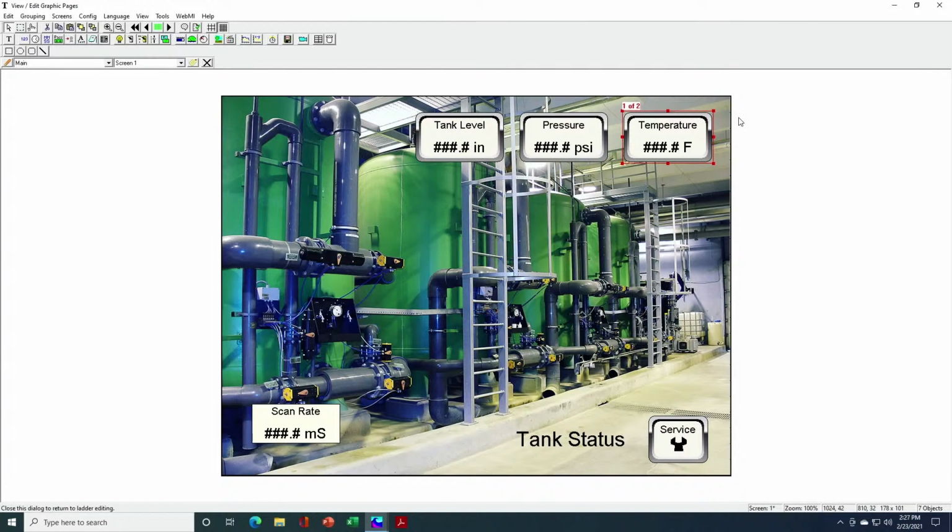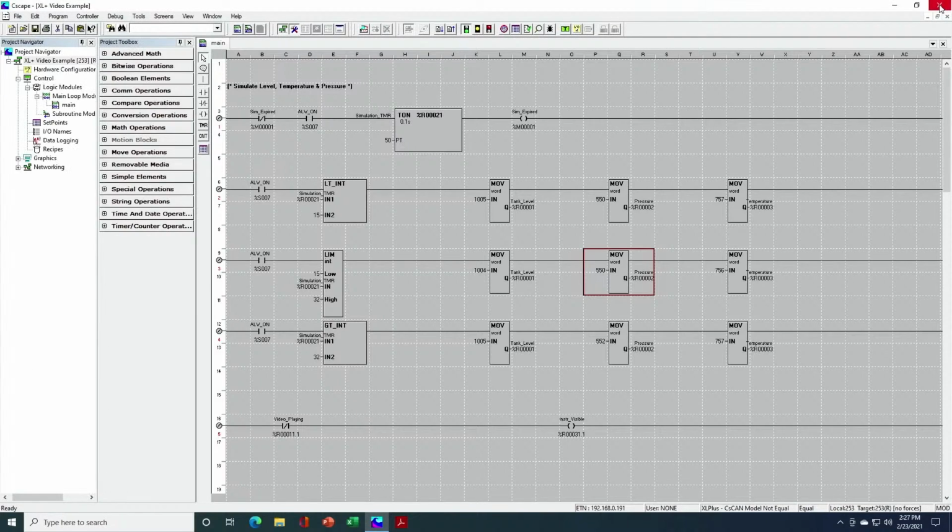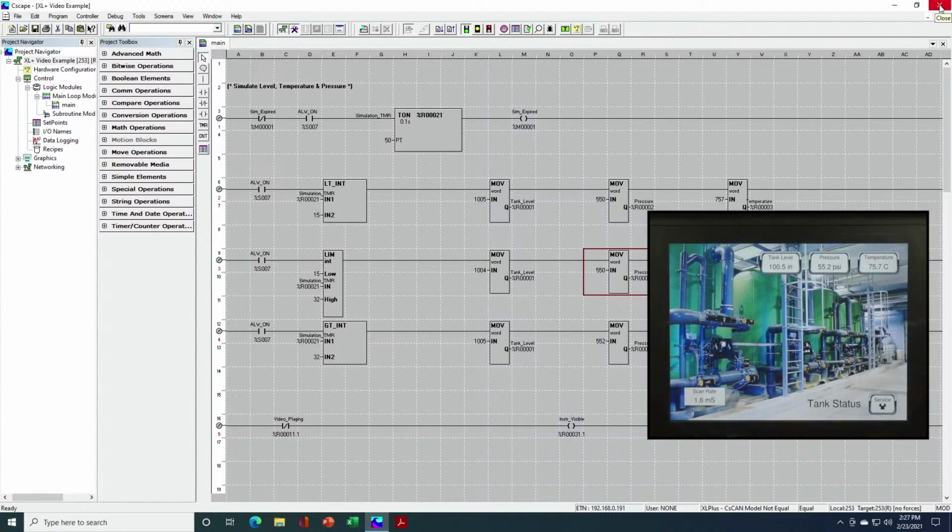And the production manager is saying, "Geez, I really don't want you to shut the line down just to make that simple change, or to stop the controller for even 15 seconds to make that simple change." So we're going to do it with live graphics download instead. You can see here in the inset the XL Plus, and that it's still running that program with C where it should be an F. But I'm going to go ahead and change that.